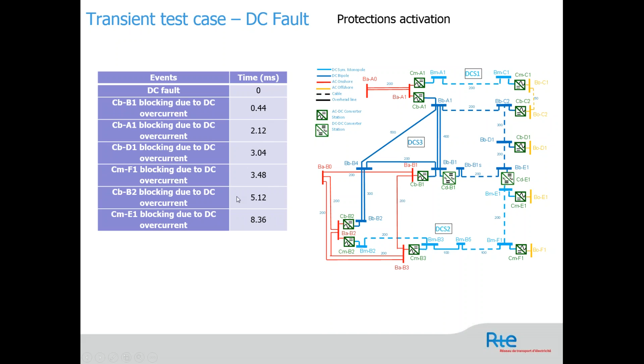If we go a little bit further than the DC fault, so you have the DC fault here, and you see what happened on the CBA1, since you have a line here, this one will trip a little bit later, at 2.12 milliseconds. And if you go further to the BBD1, CBD1 here, which is a little bit more remote from the DC fault, you can see that the time of tripping is longer and longer. So here we are imagining that if the DC fault remained for 3 milliseconds, only the converters in CBA1 and CBB1 will trip, and the remaining ones will still be alive, will not trip. Okay.